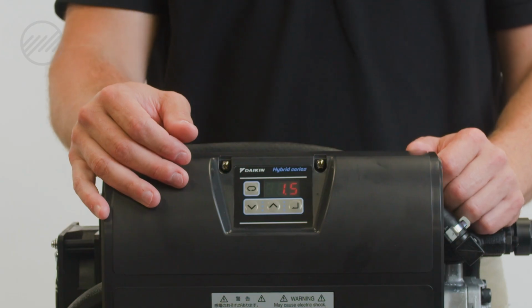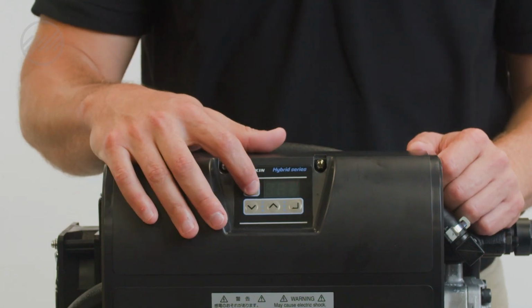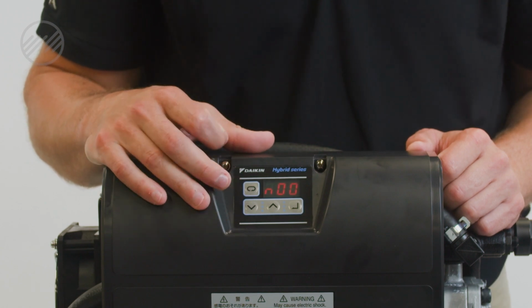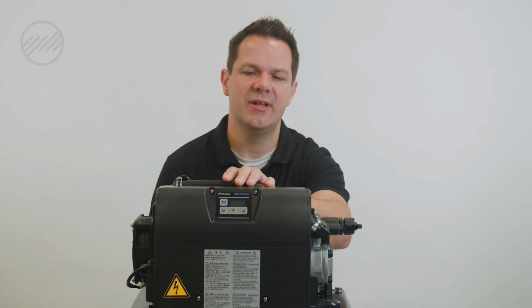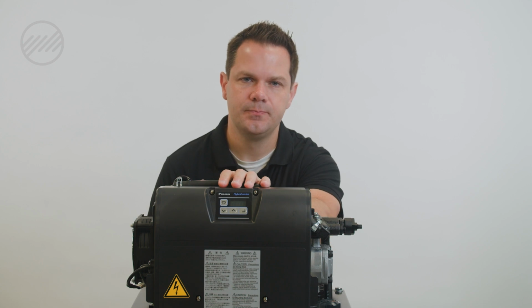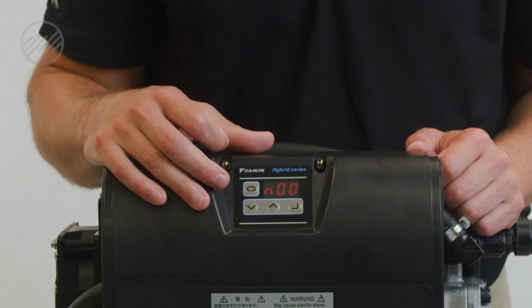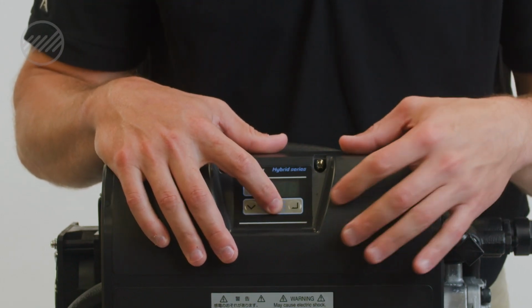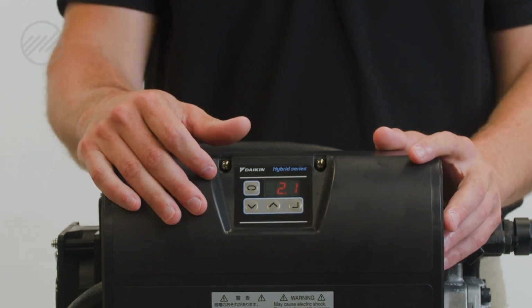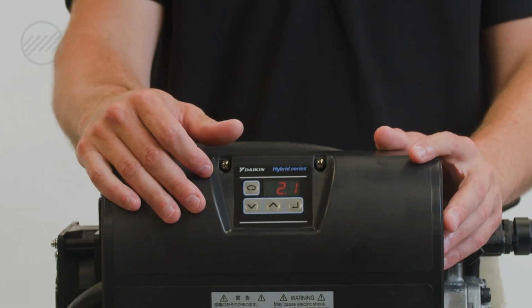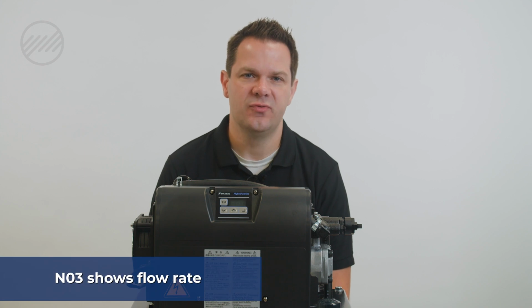To access our monitor mode, we'll push the menu key and hold it down for 2 seconds. It will then flash N00. Using your up arrow, you can scroll up to N03 and hit enter, the backwards O. That'll show you your actual flow rate through the pump.